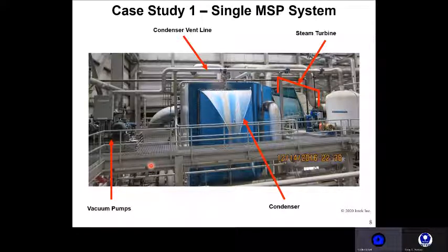Due to limitation on space and access to the lines, a single Re-Evac probe system was used. This meant that the search area could not be as easily localized. However, it is a much smaller condenser than a typical coal or nuclear unit, meaning that the entire unit could be checked with helium in one day.